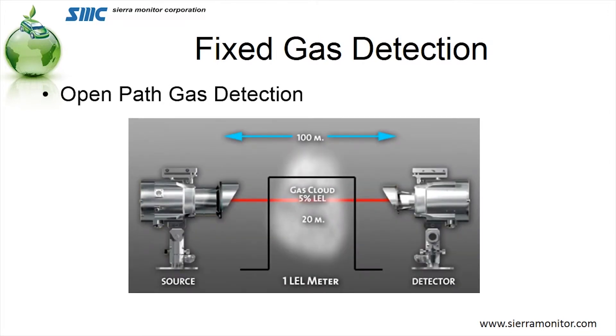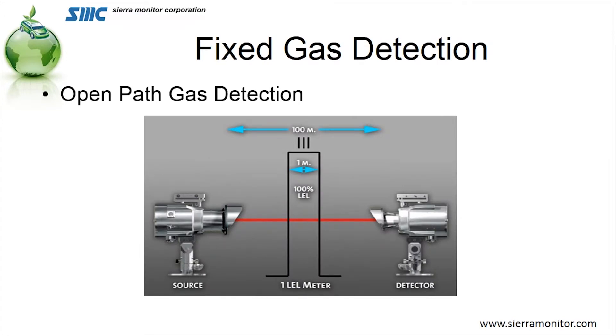Open path, by nature, has a beam that it's looking for a cloud of gas in. We talk about it in terms of LEL per meter. If I had 5% LEL gas in 20 meters, I would have one LEL meter. So if I was one-twentieth of the way to the explosive level in 20 meters, I would be one LEL meter. Conversely, if I had 100% LEL — enough gas to be explosive — in one meter, I'm still one LEL meter. I don't know where I'm at in that beam, but I'm now at an explosive level. So you can see there's a little drawback to open path technology.